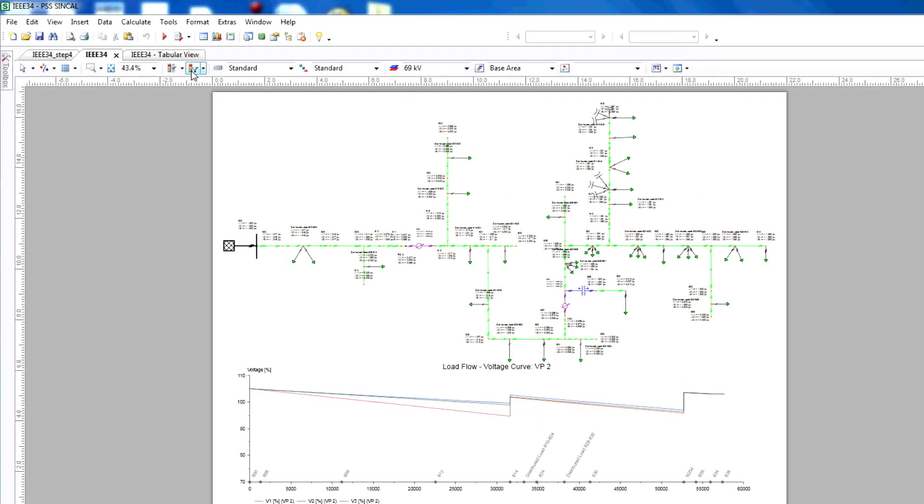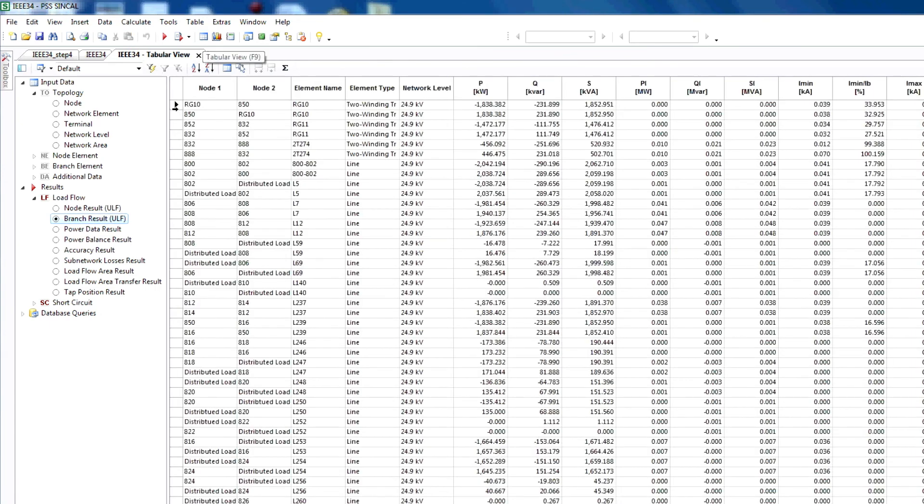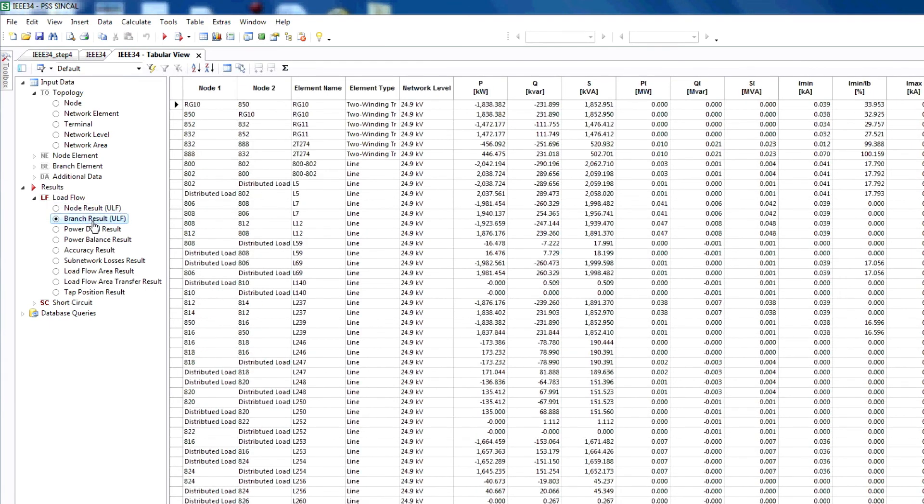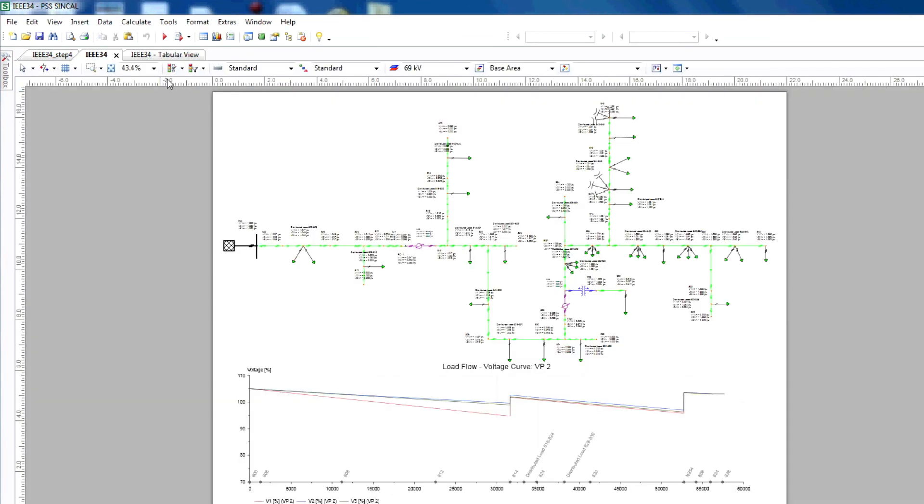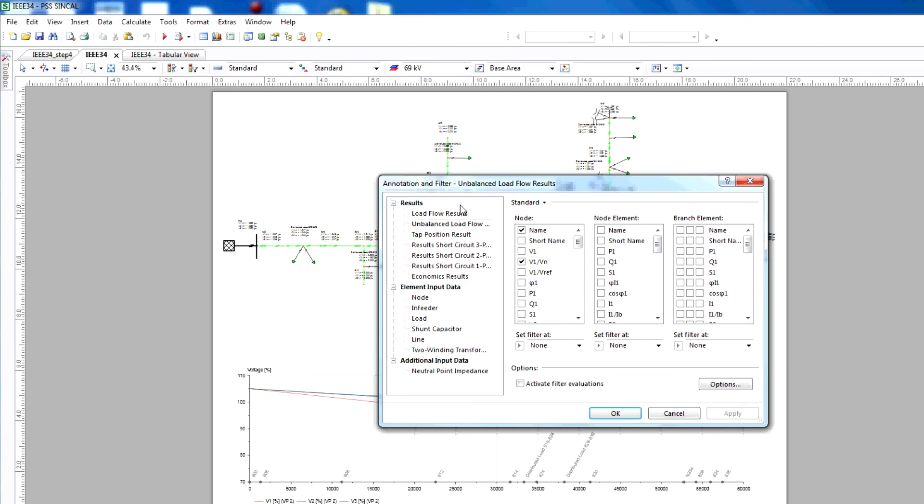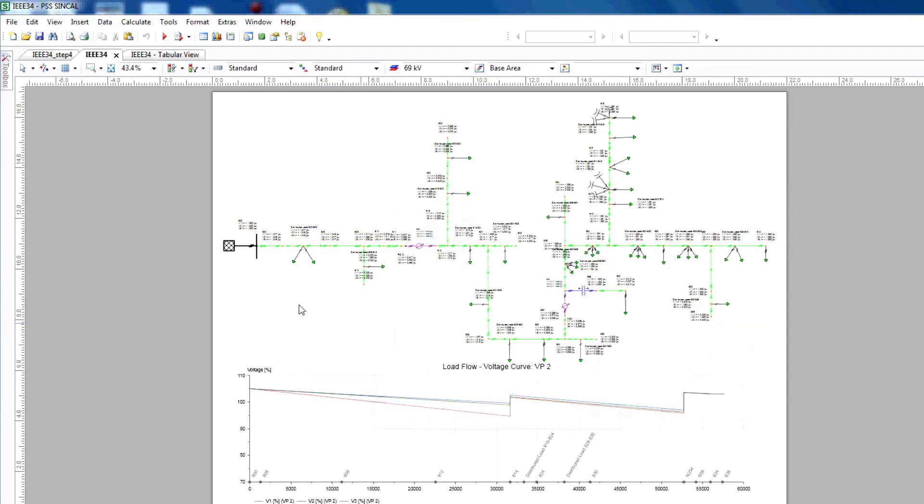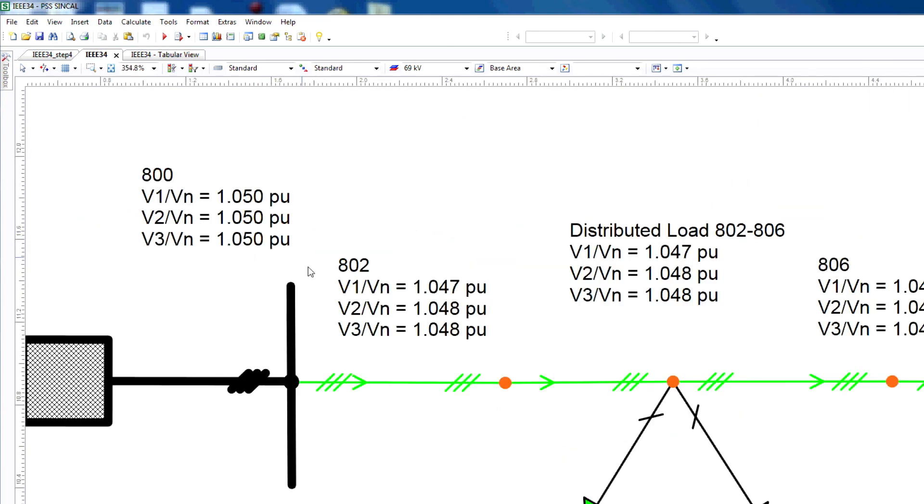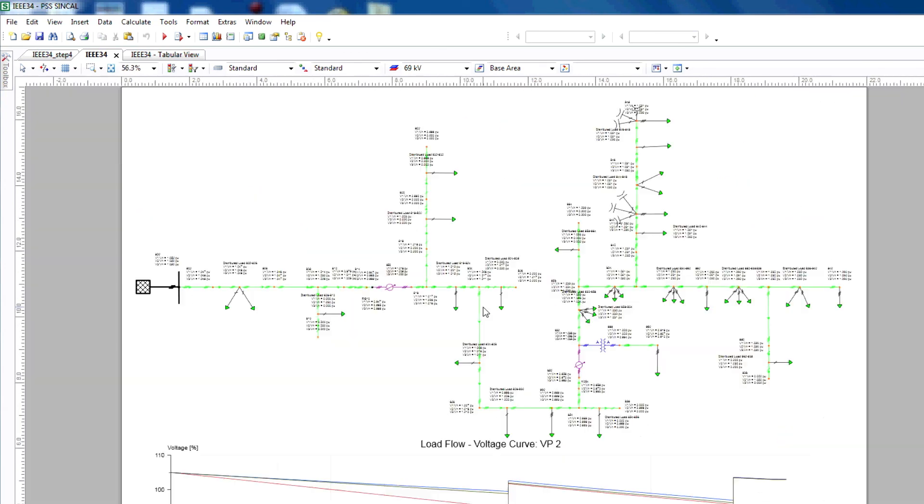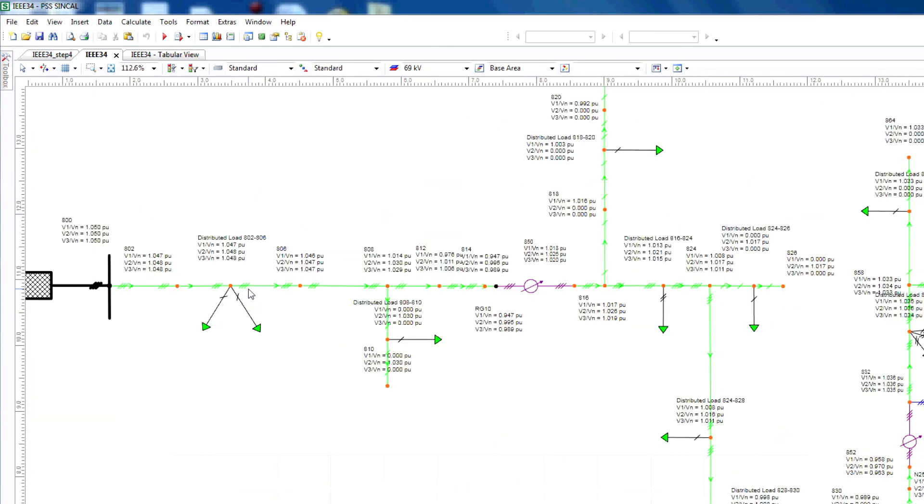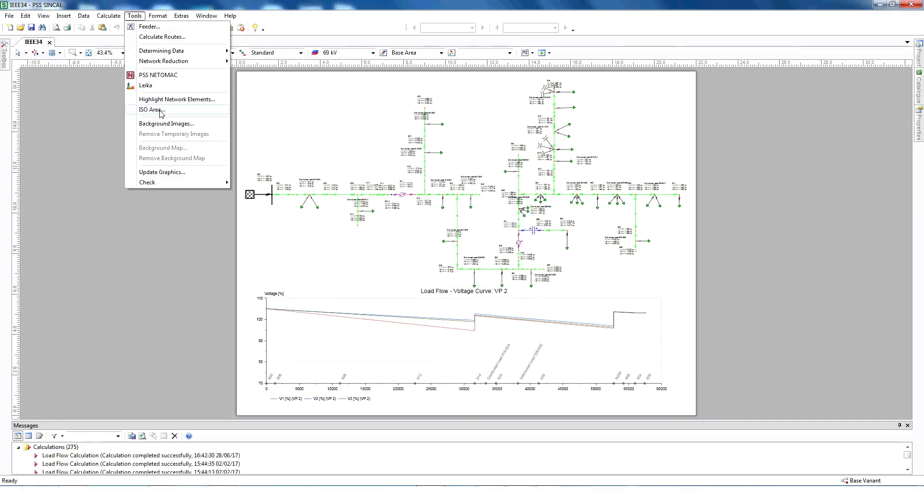Load flow results can be seen in detail by selecting tabular view. Choose node results, branch results, or any other option to see the results you need. The annotation and filter option allow you to see the specific data result in your SINCAL model. For example, a voltage profile shows how the voltage behaves from the source to the end of the feeder. Similarly, we can see the voltage graphically by using ISO plot.